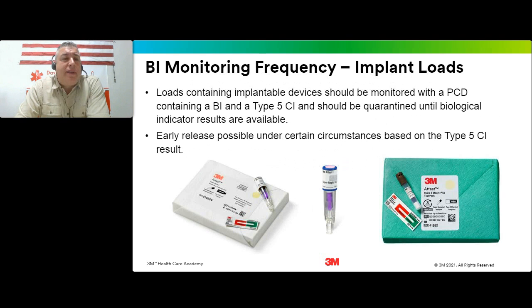And eliminate this - we talked about the other devices. Loads containing implantable devices should be monitored with a PCD. So it's important to always remind you that in case there's the need for an implantable device, even if you have a BI on the cycle, and even if you have a rapid readout technology, it may be needed in an emergency. We live in an emergency world, so to speak. There could be trauma, there could be emergency cases where life and limb are on the line, and the doctor may need that set.